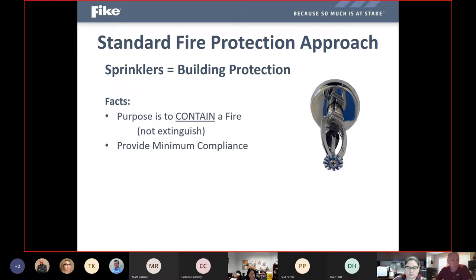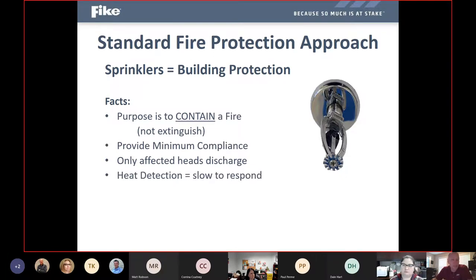So, sprinkler systems provide minimum compliance with the codes. And again, only the affected heads will discharge because each sprinkler head has a fusible or thermal link on the bottom. And if that head does not melt off because the heat is not hot enough to melt it at that specific area, the head's not going to open and water will not come out. So the only way water discharges from a sprinkler head is once that link has melted and fallen off of the head.